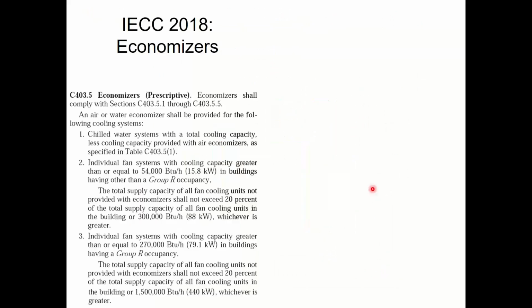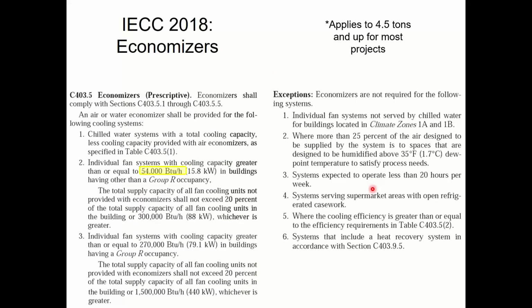We'll skip those for now. Economizers are code required. For the International 2018 energy code, if the system is 54,000 BTUs and larger, what does that mean? That means 4.5 tons. So 4.5 ton systems and larger have to have an economizer. Systems that are smaller than that do not have to have an economizer. There are some exceptions to that rule. Most of those exceptions do not apply to you.